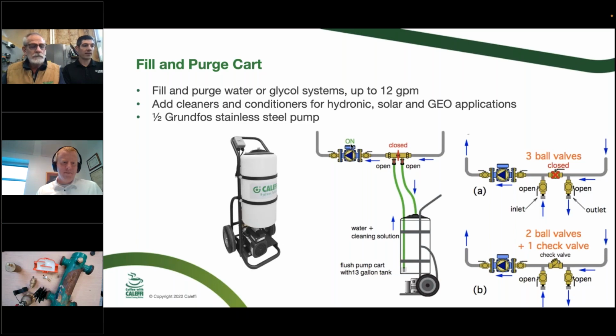So is the system pump a good pump to fill and purge a system? If it's sized right, probably not. In most cases, these circulators are sized for lower velocities, so it keeps the velocity noise to a minimum, and they're still good for moving around air. But if you're talking about purging out systems for dirt and debris and things like that, a lot of times those circulators don't have the velocity through those systems to be able to push that stuff around. That's where a flush cart.